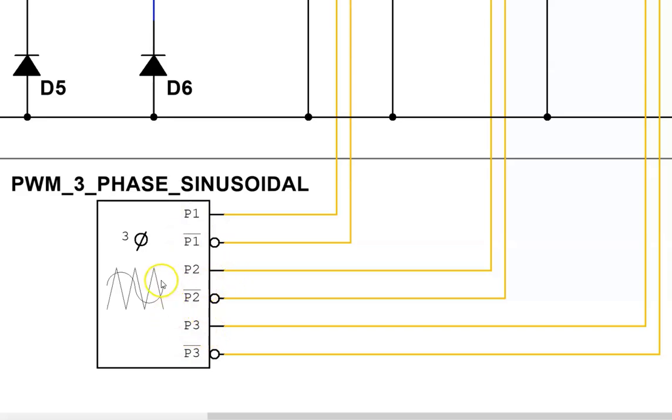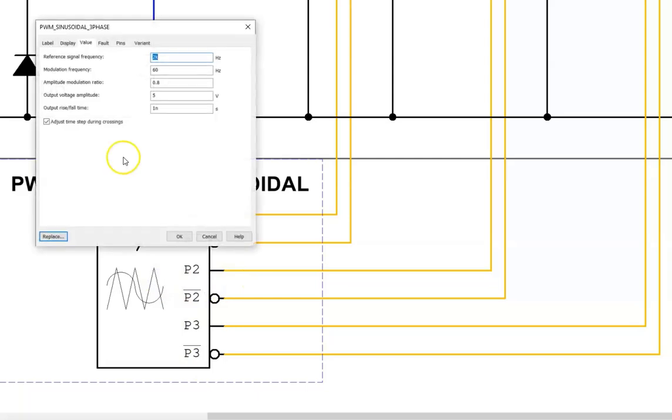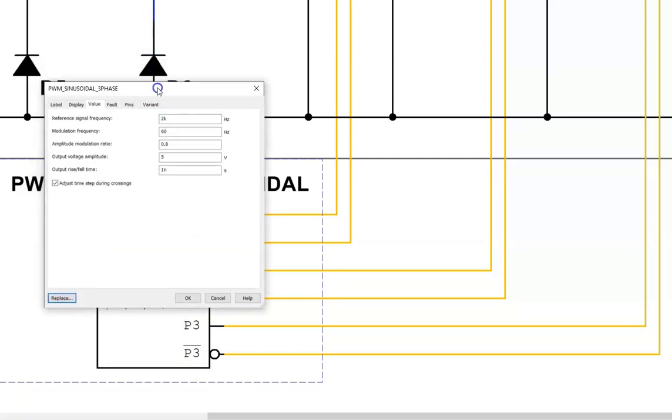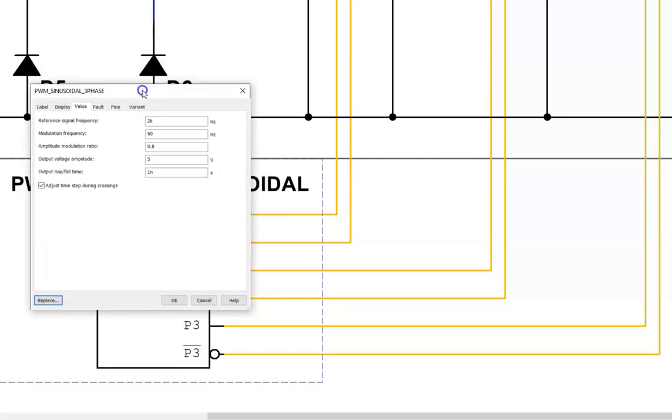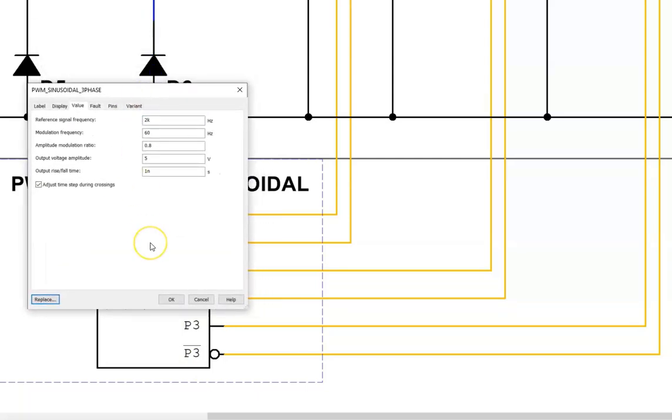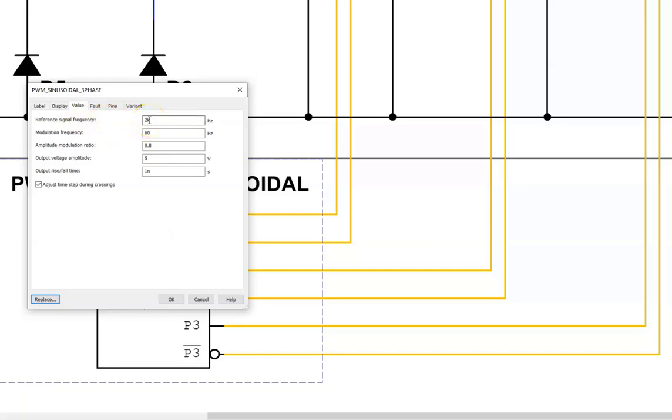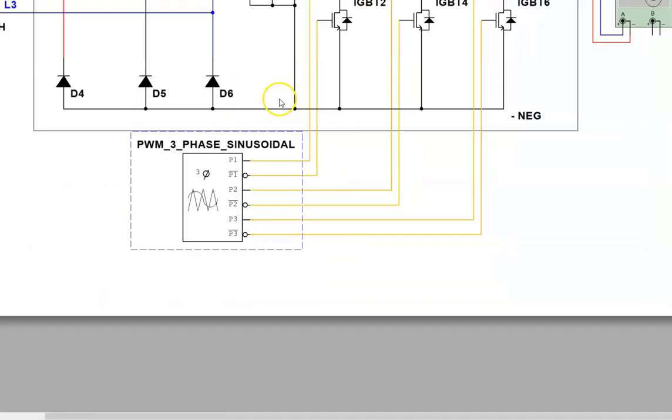Now if I open this up, there's a box that allows us to make adjustments. We can change the switching frequency. It's called the reference frequency. But if you were programming it on the drive, it would be called a switching frequency or carrier frequency. I can change the speed from 60 hertz to 30 hertz using the modulation frequency.